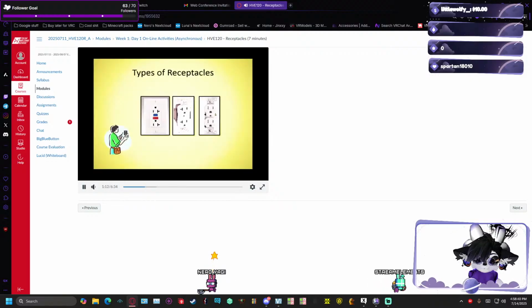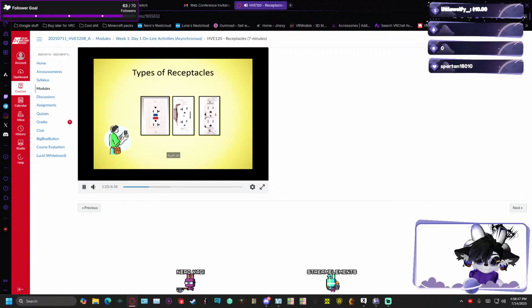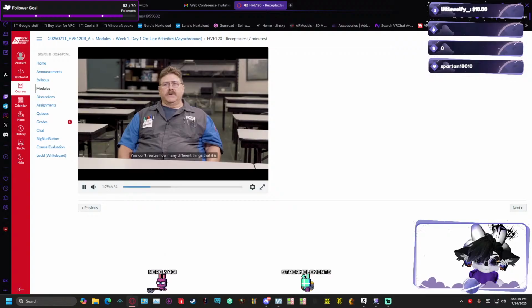The other receptacle on the far right would be a tamper resistant one. If you look at it real closely, you can see the insert of it has a milky white in it, and that's so children cannot put anything that would conduct electricity into that receptacle and possibly get hurt. On the receptacle itself, you don't realize how many different things it is designed and engineered to do, and the purpose behind everything is safety and function.